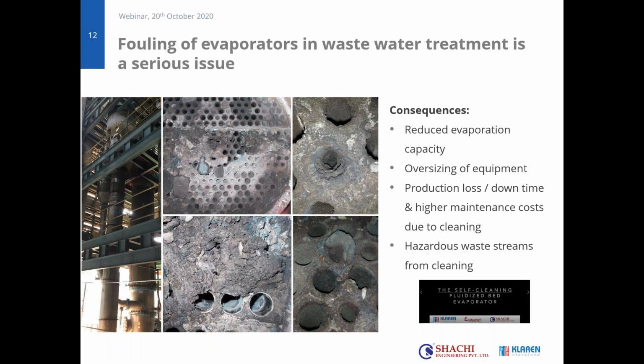A slide I normally start with in fact shows what problem we try to solve. What we see in the treatment of wastewater is that many plants experience severe problems with fouling, also sometimes called clogging or plugging. The fouling initially reduces the heat transfer, and by reducing the heat transfer, of course, the evaporation capacity of the plant is affected. But at the end, complete tubes could be plugged, even limiting the flow, and even furthermore limiting the capacity.